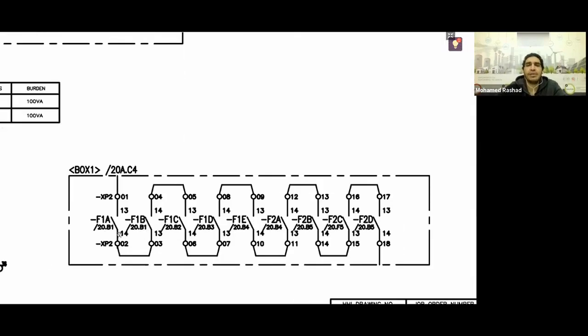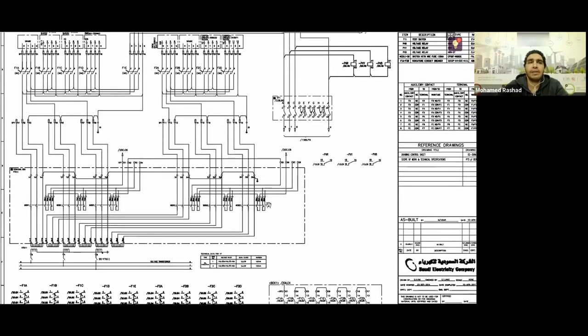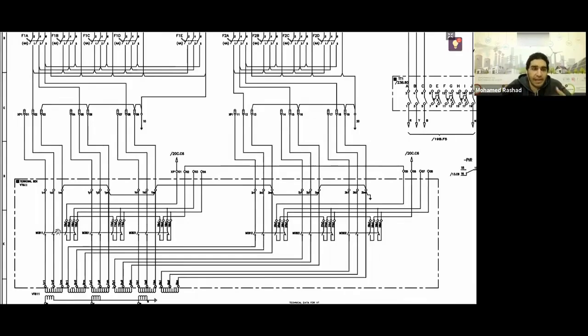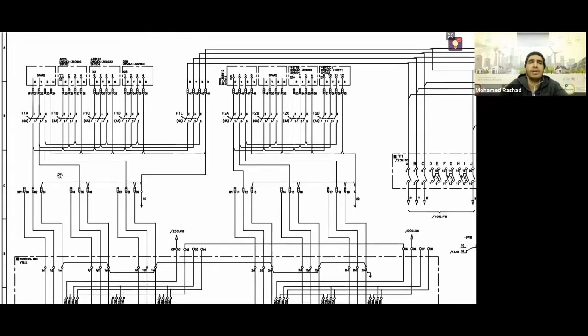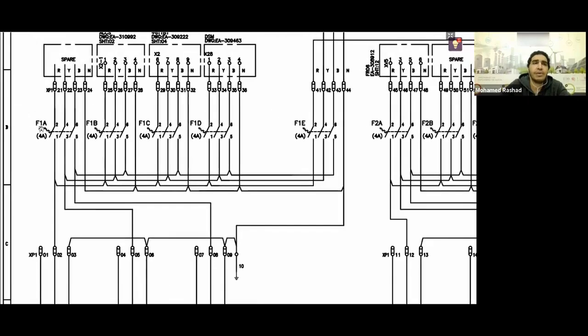What is this so we don't forget it? What is this that is located below us? Here you will find a set of all that must be connected. They all must be connected, and of course these are all a set related to the distribution of what? The distribution of the VT circuits inside the LCC. Where is the MCB itself? Meaning the context of the MCB here. Where is the MCB itself? Here it is, isn't it? This was the MCB of the box. Now exit from the box. You exited from the box, and here you are in the LCC. You will find F1A, F1B, and F1C. These are all the miniature circuit breakers.